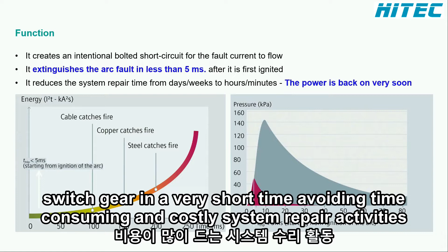Words are meaningless when it comes to arcing faults. Here you will watch a video shot from one of our development tests with SIQuench located in the busbar compartment of a 12 kV lineup. Arc ignition was in the cable compartment of the cubicle in the middle.